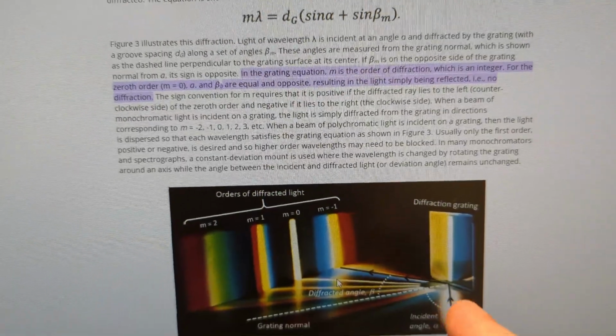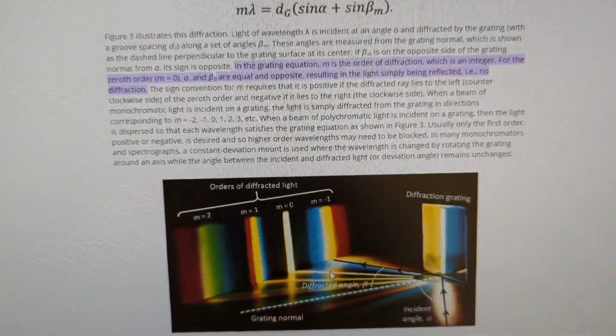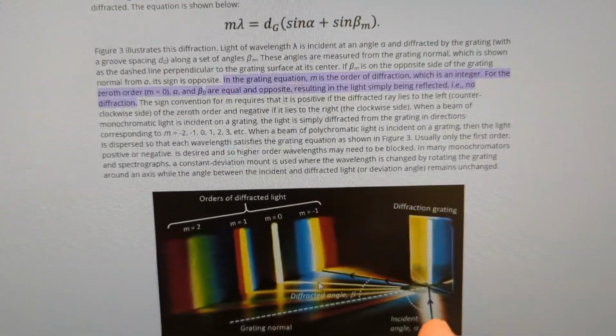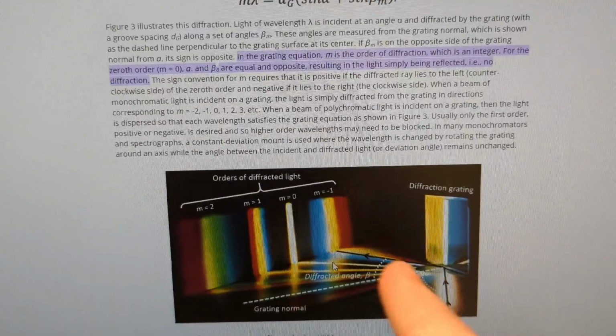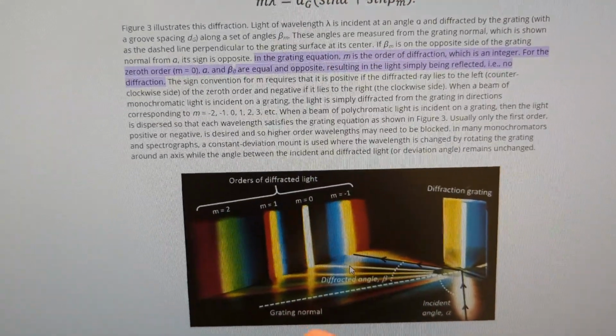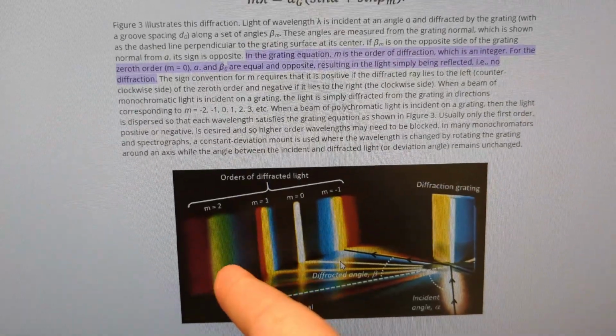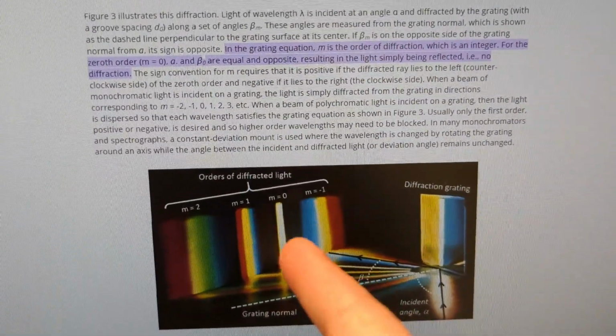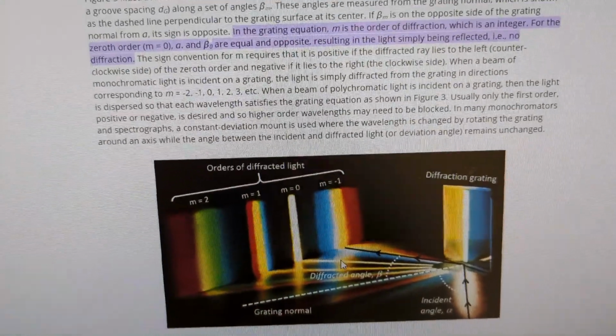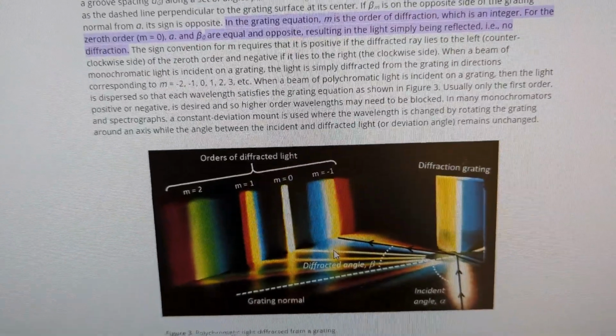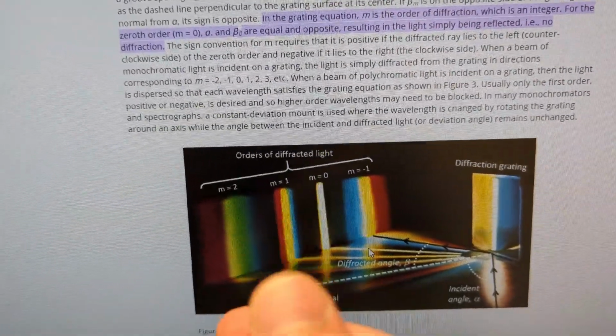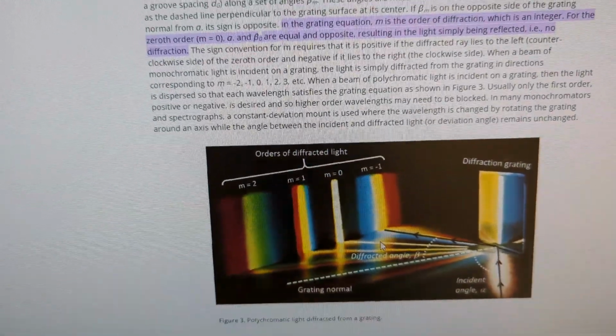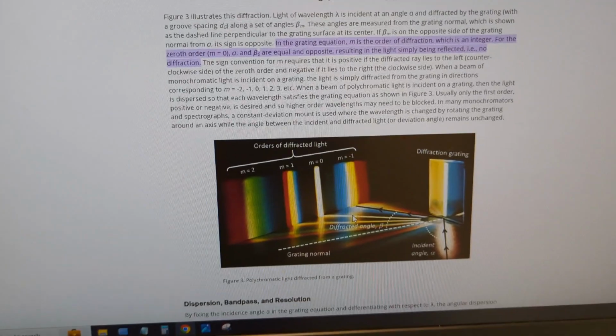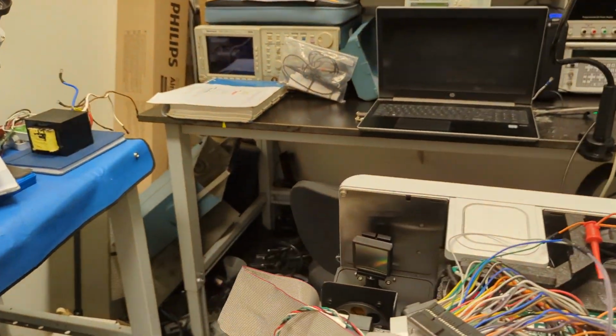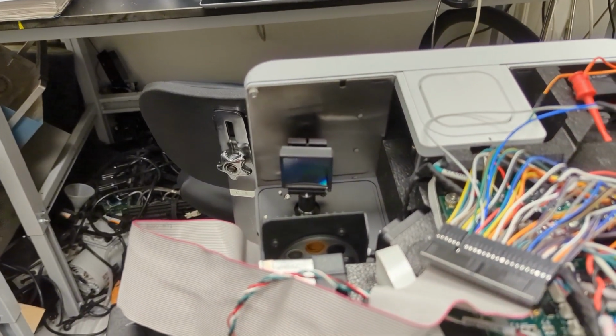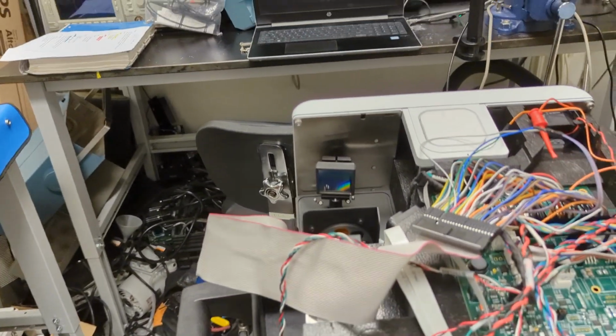That's because, now, this is how I understand it, but if I'm wrong, please mention it in the comments. The zero order is basically just the light getting reflected. It's not getting diffracted, so it's not being broken up into its composite wavelengths. And so that's why it doesn't look like a prism like these other ones. And so the instrument is using that zero order to then determine the accuracy of all of the wavelengths being diffracted. It's using that as a reference. And so that gives you a big clue for calibrating or adjusting the diffraction grating.